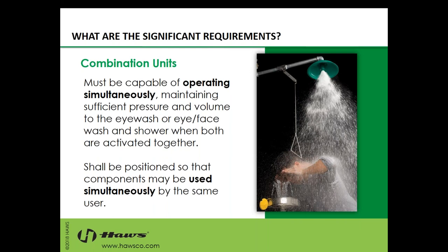There's not enough water to supply both, and nobody's using flow controls to limit the amount of water coming out of the shower. We have 30 plus GPM coming out of there. It's sucking up all the water from the unit, and there's nothing left for the eyewash or eye face wash. So make sure you're paying attention. That is a really severe problem.